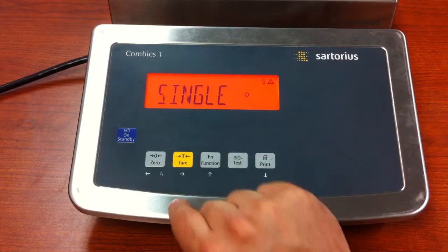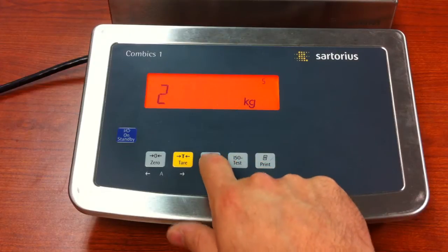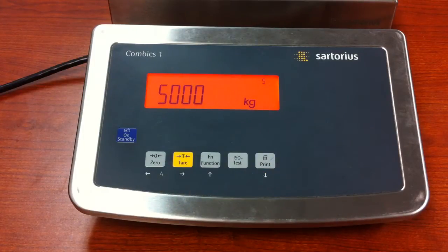It'll bring you to ranges — press the tare key again. Single is the most common; we're going to keep that. Press the tare key, and now this is where we input our maximum capacity. This one is set up for 10,000 kg, but I only need 5, so I'm going to change that to 5,000. Press and release the tare key.